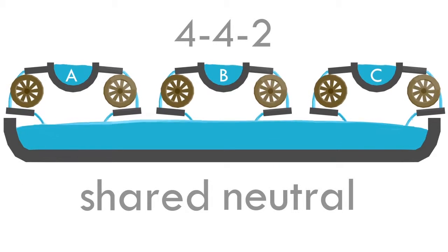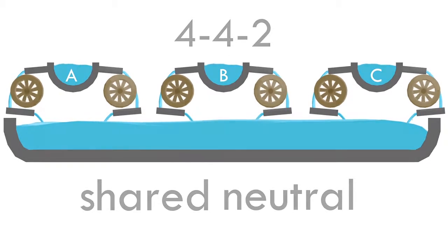Or as a shared neutral, which is used by all three phases in one run back to the panel. This is a four-wire system. Fewer wires means less cost. However, it's entirely up to the local electrical code to determine the neutral type required.